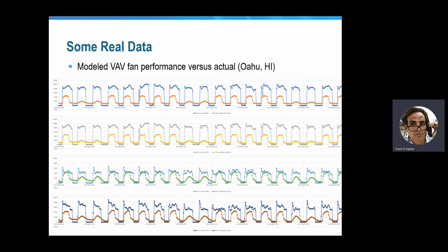First, I'd like you to look at the width of each one of these days. Our energy modelers often assume that we're going to run from 8 a.m. to 5 p.m. In our buildings, that's almost always wrong. Most of our buildings start up at 5 or 6 o'clock in the morning. And then we do run them past 5 p.m. We leave the fans on for the cleaning crew so they can run till 7:30 or 8. That's important because that's the difference between 200 hours a month and 300 hours a month of fan power.